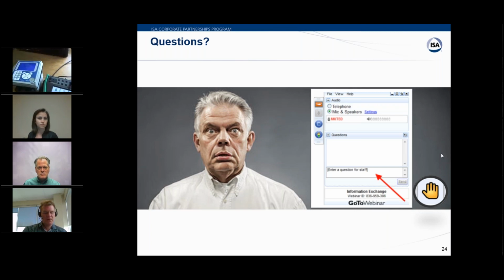Yeah, so the response time will be in every manufacturer's data sheet. It will be on the data sheet for the product when you're buying it, what the expected response time is, often shown as a T90, so 90% of the response. And with the calibrator, you could even test one manufacturer against another. If you have both available, you could put them in one pH buffer solution, move it to another one, and time it yourself, see which one has better response or whatever property you're looking for.